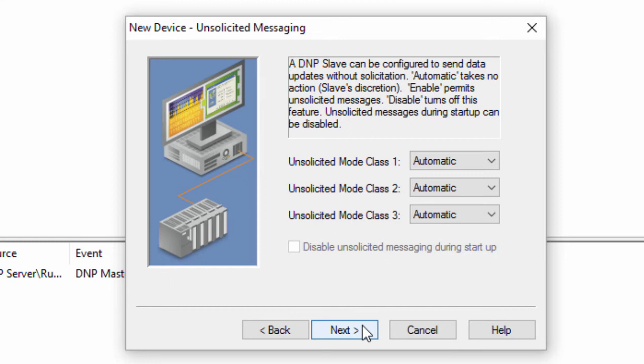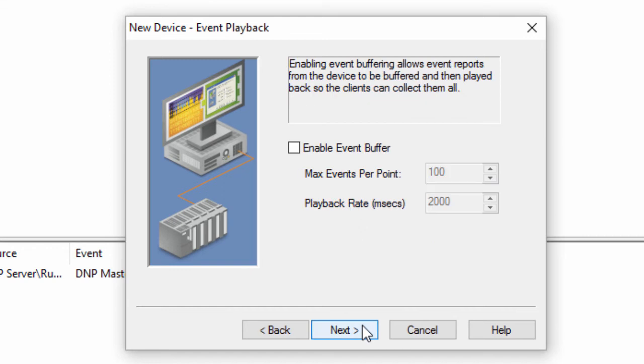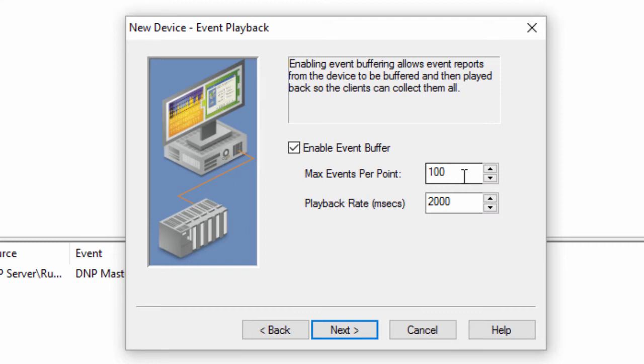The deadband settings can prevent you from receiving every data change, which can be good or bad based on data reporting needs and bandwidth limitations. Click Next to specify the event playback settings. To assure retrieval of all buffered events, the client must have an update rate that is at least twice as fast as the playback rate. If the client's update rate is slower, it effectively overrides the playback rate.